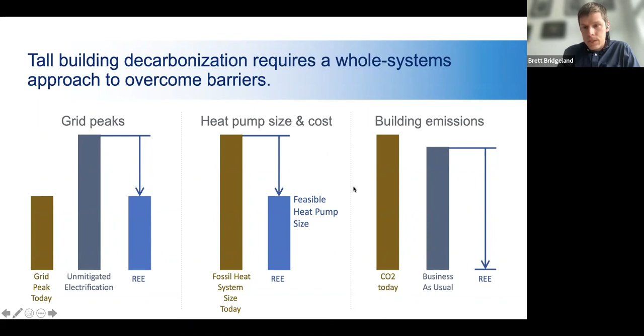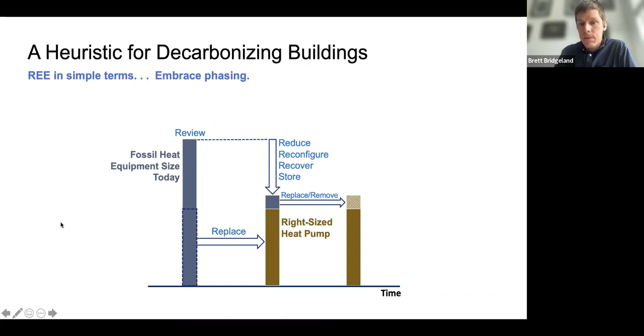There's a certain size heat pump that makes sense for these buildings technically and economically. To bridge that gap, there are enabling steps we're seeing examples of through the Empire Building Challenge projects that reduce energy consumption, reconfigure systems, and take advantage of energy recovery and thermal storage to limit the size of heat pumps needed. Then we can talk about replacing heat sources, whether gas boilers or gas-fired district steam, with various types of heat pumps.